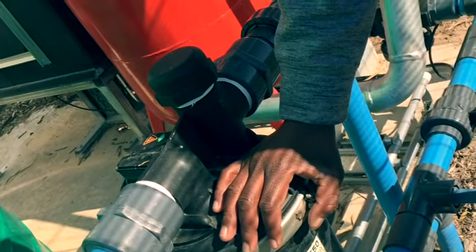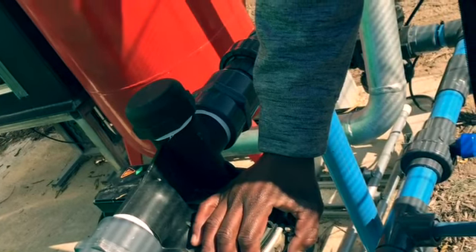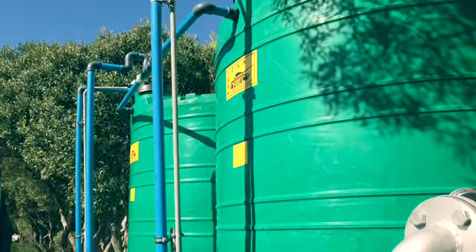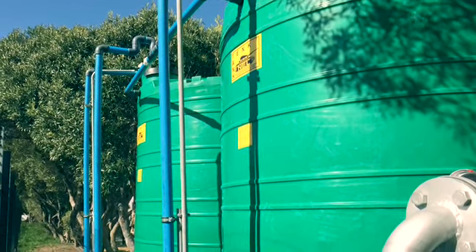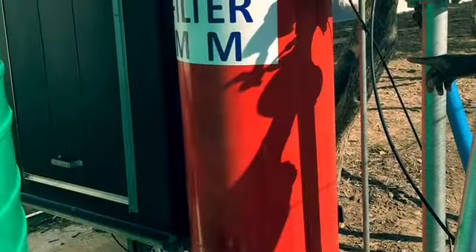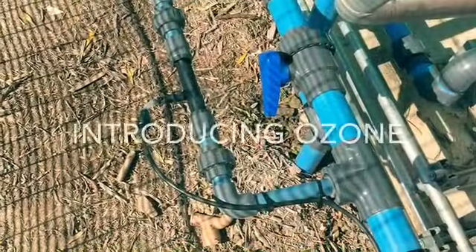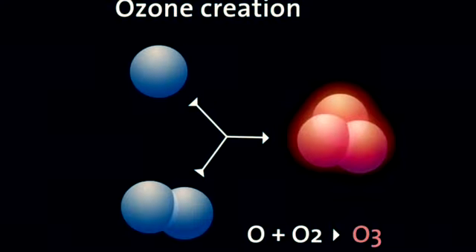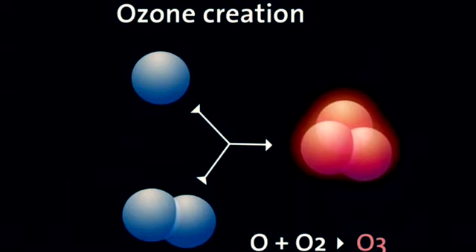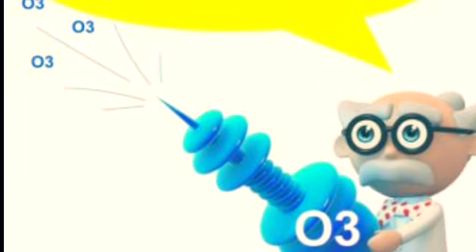Then the water is pumped through a black strainer to remove any big waste solids to the first big green tank that can store up to 10,000 litres. From this green tank, the water is pumped through a red filter after which ozone is injected into it. Ozone is preferred as an oxidant because it is easily available, cost effective, leaves no hazardous chemicals as by-products, and is the most effective.